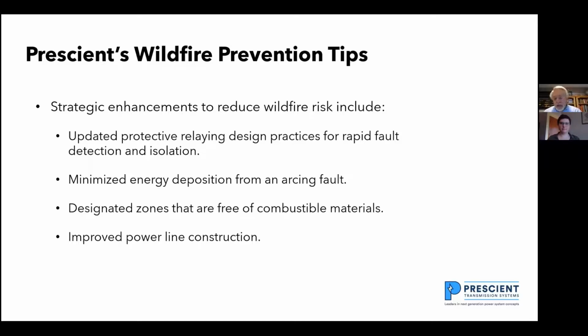fault igniting a wildfire. Now, the 100 milliseconds is based on typically circuit breakers being 3-cycle circuit breakers, which means they operate in 50 milliseconds. And the relay time is about 20 milliseconds. So I'm thinking I should be able to clear faults in 70 milliseconds, but I'm plotting it at 100 milliseconds. And I want to designate combustible material free zones, and I want to improve power line construction.